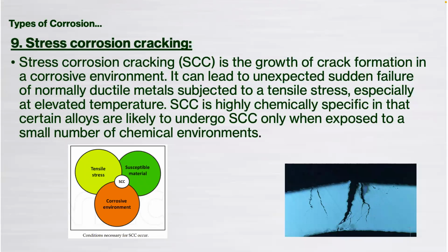You need a tensile stress, a susceptible material, and a corrosive environment. So a tensile stress is our system, it's under pressure. So the material is under pressure. A susceptible material, so let's say in this case, a non-DZR brass, and then we have a corrosive environment. So to give an example, this might be a chilled water system.